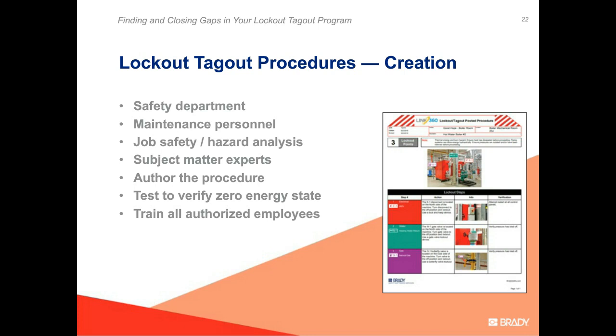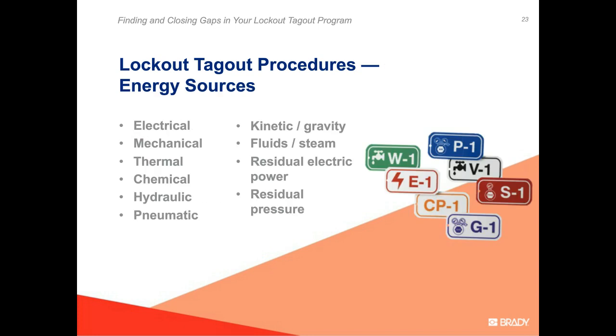Lockout tagout procedures have energy sources, and these should have tags that identify which isolation point has each type of energy. Each energy source has different ways to dissipate and isolate it. For electrical, you're looking at service panels, outlets, transformers, motors, and capacitors. Almost every lockout tagout procedure you write will involve electrical energy. It's typically your most common and most hazardous source, usually listed as your first step, and it needs to be taken seriously, following all electrical code when isolating those points.